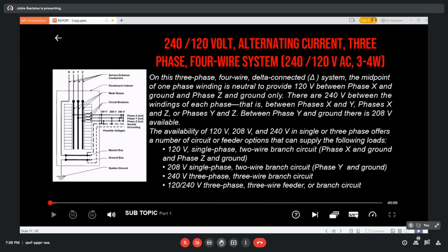On this three-phase four-wire, delta-connected system, the midpoint of one phase winding is neutral to provide 120 volts between phase X and ground, and phase Z and ground only. There are 240 volts between the windings of each phase, that is, between phases X and Y, phases X and Z, or phases Y and Z. Between phase Y and ground, there is 208 volts available.